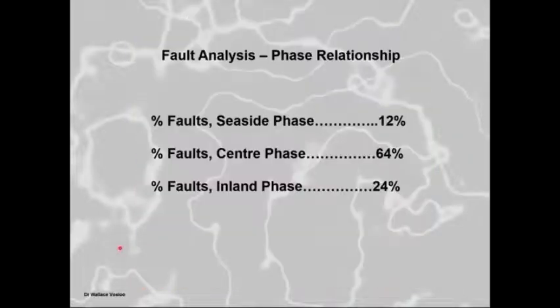Oh boy, okay. So then we started to analyze where the faults are. Now you see, the line runs in such a way that there's a seaside, a center phase, and then there is the inland phase on the inland side. Now, when you take a look at the faults, you see the majority of the faults, it's not on the seaside. It's actually on the center phase. So 64% of the faults are on the center phase. Now, why is 64% of the faults on the center phase? And then further, inland, it's worse than what it is on the seaside. It's not a pollution problem. There's something else. Show this to the guys. Blue insulator, please. We don't want anything else.